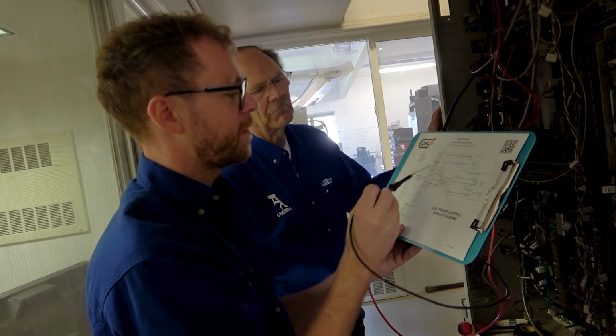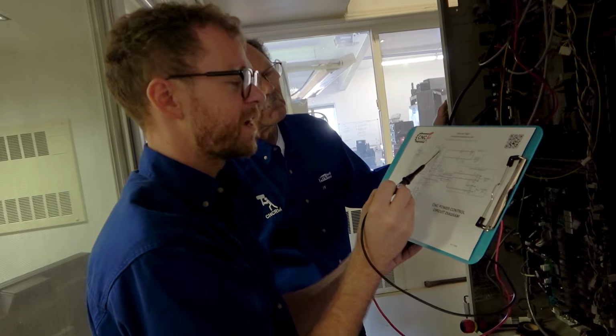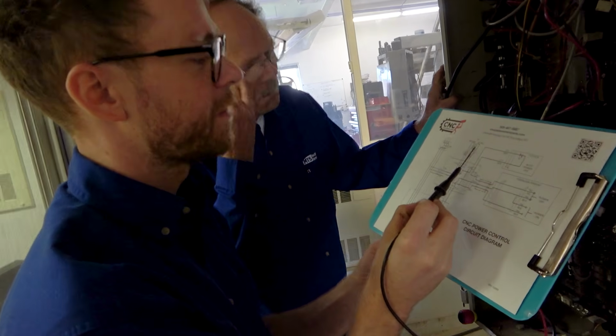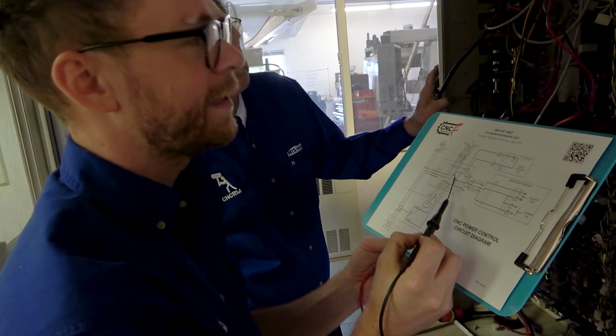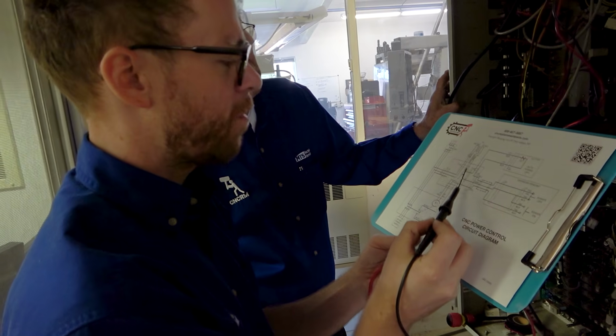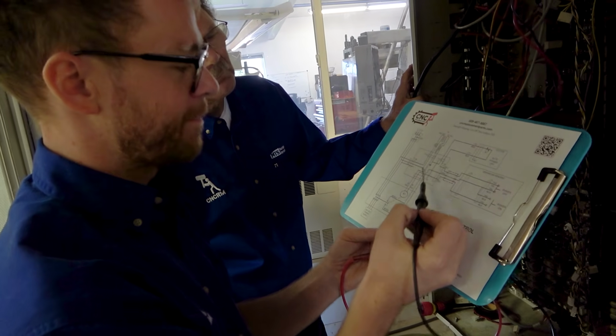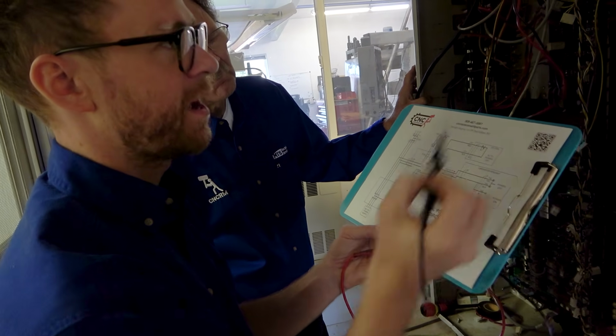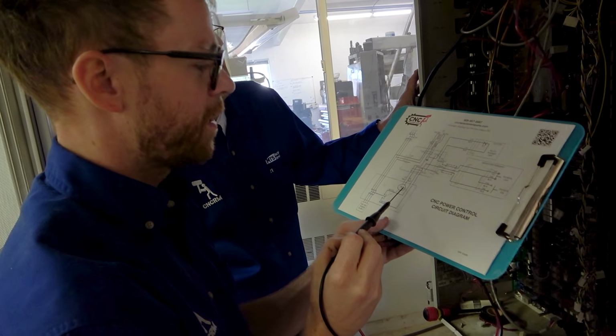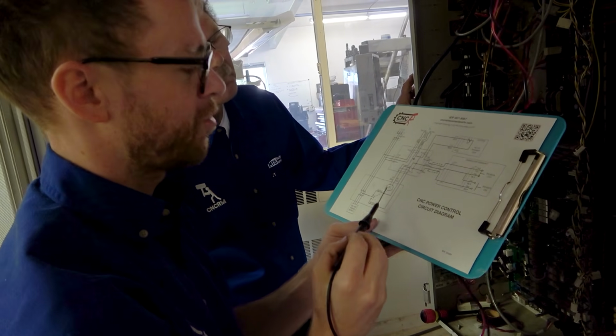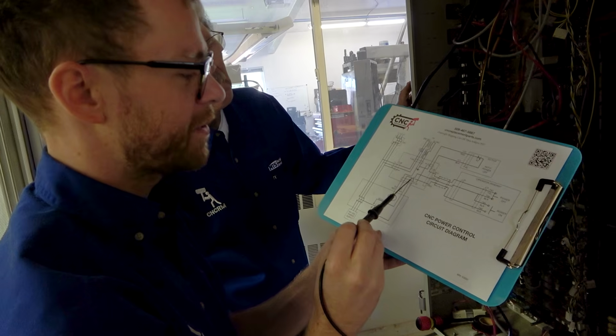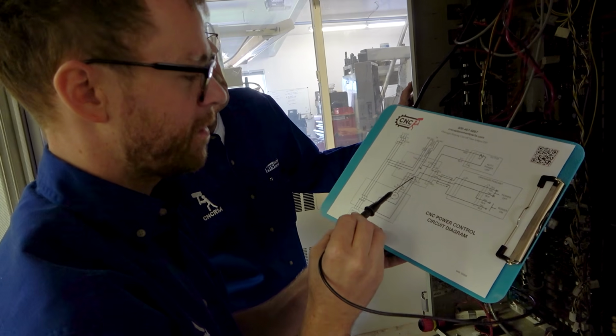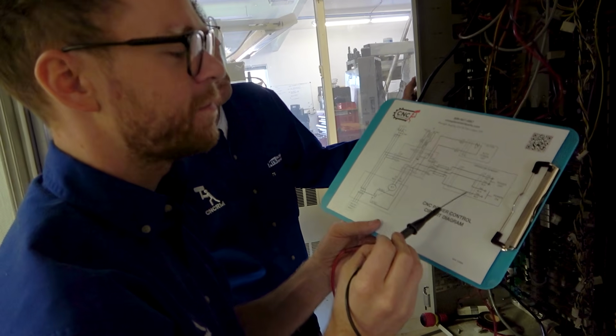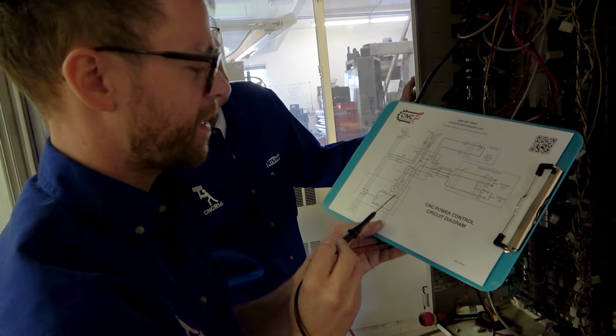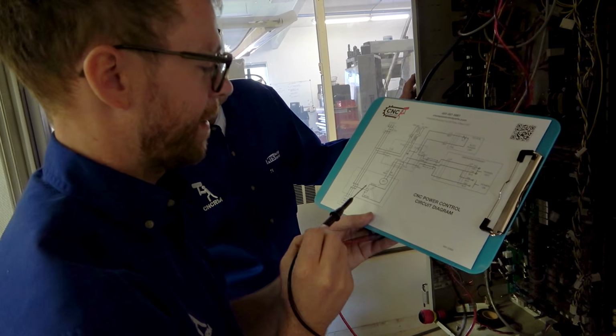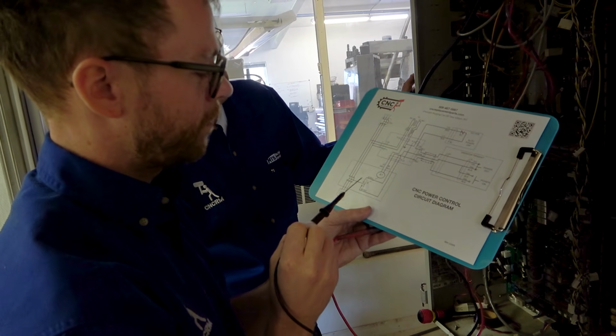Power comes in, it goes to a transformer. The other side of the transformer is 24 volts AC. On the other side of that transformer, one leg of it is grounded. The power on the other side comes back to the power distribution card, goes to the K1 contactor, goes through the coil of the K1 contactor and comes back to the power distribution board. Then it splits right here. This is important. It then goes all the way to the pendant to the on button and splits and comes down to the K1 contactor. It goes through a normally open contact.